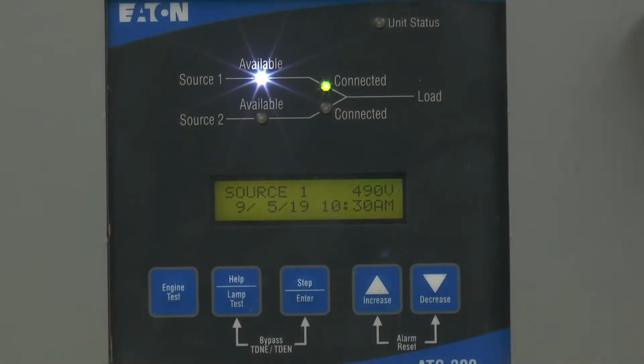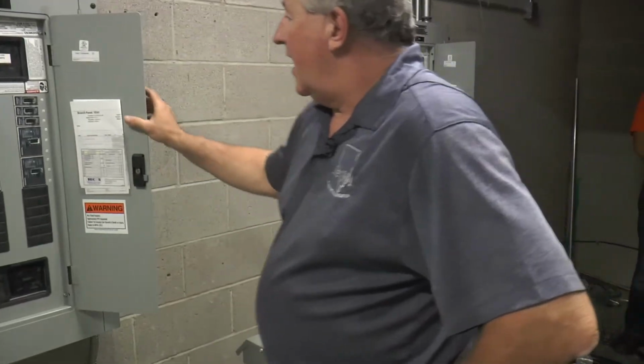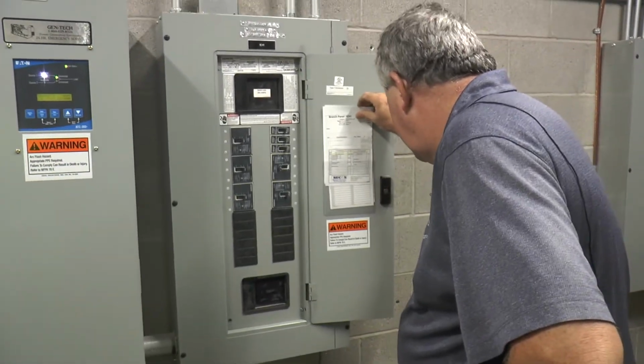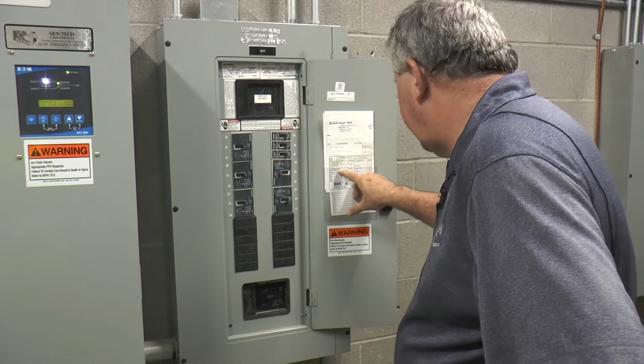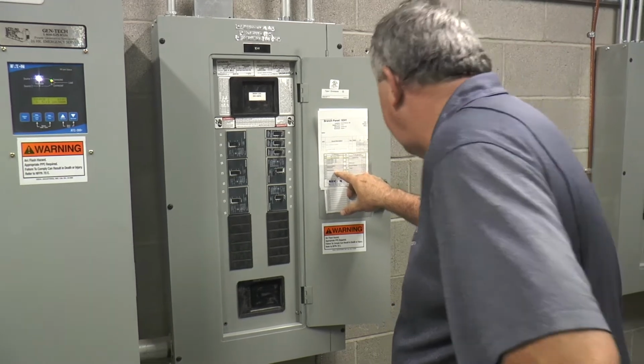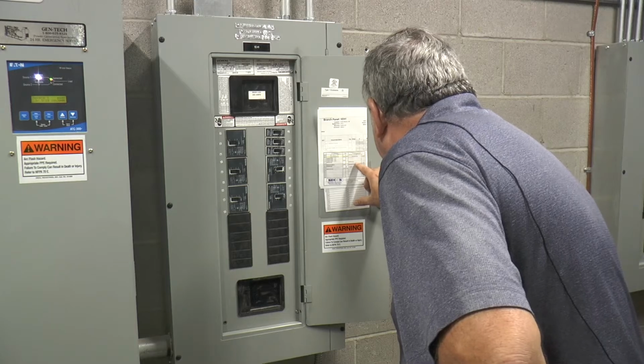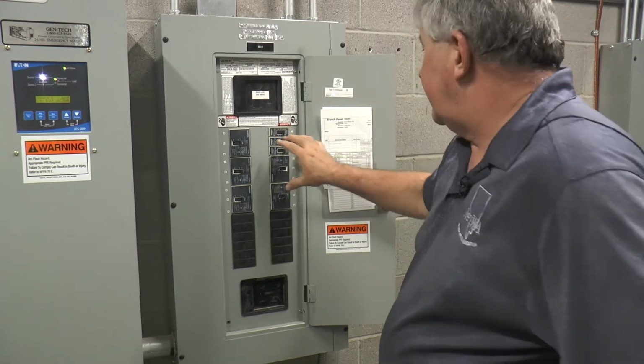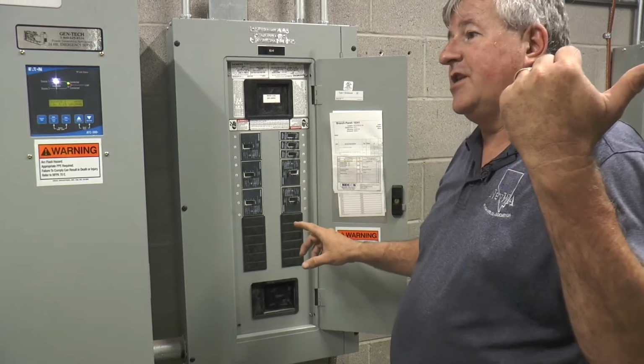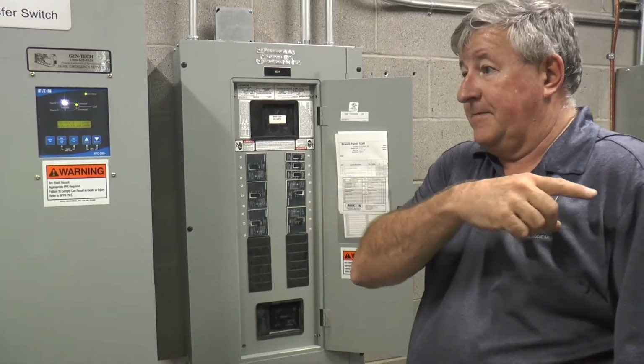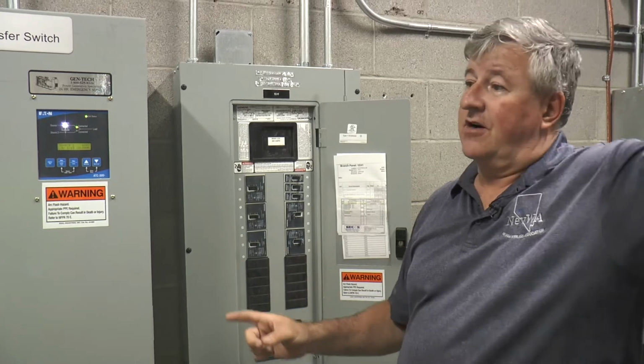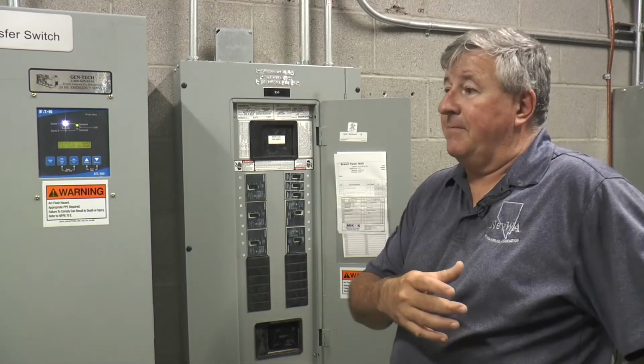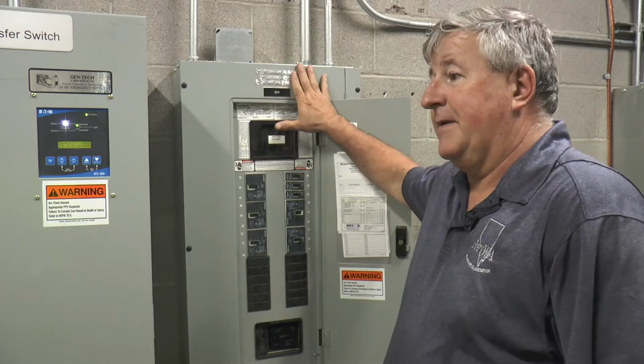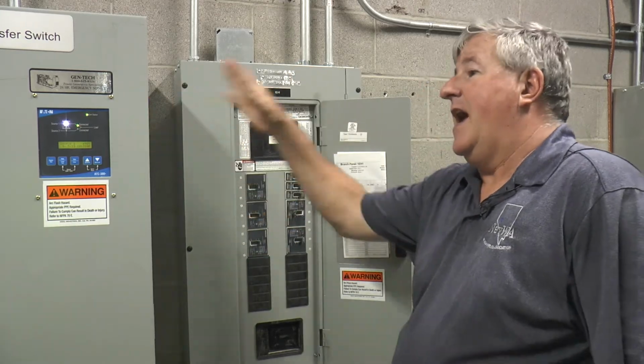This is the life safety transfer switch, which feeds the life safety panel on high voltage through a transformer to the low voltage panel. On this panel, they have 3 transformers and some generator loads. We've got the pumps and the fan. Let's see, and probably, yep, coolant pumps. This is the panel that's feeding the load center on the generator set and all the circuits for the pumps. So it leaves here, goes to the starter, out of the starter to the pump. So if you have a problem with the pump or starter not having power, this is where it's being fed from. So it has power on emergency and on utility.